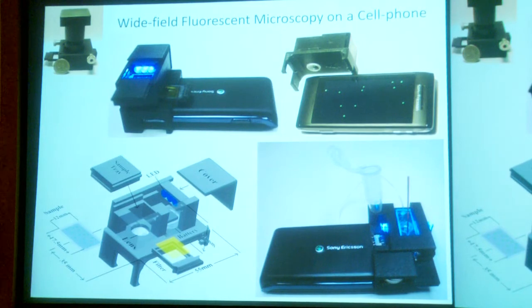It's quite different in physics from what I've been introducing to you so far, in the sense that this is actually around 30 grams, attaches to the back of the existing camera unit, and the specimen is inserted from the side. There are some light sources here, which are also LEDs, which are used to excite these fluorophores, these chemical components which emit light once excited. The sample is inserted from the side, but it also acts like a waveguide, so that the excitation is uniformly distributed through the sample, which makes us quite successful at getting rid of this excitation light using a very inexpensive filter. That's a $1 filter that's inserted from the side, which gives us a large rejection of the pump and a nice dark field.